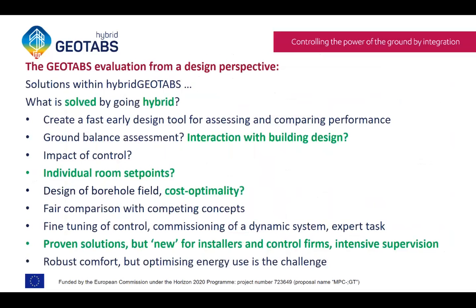So if we go hybrid, if we add that second system, what have we solved? We've solved the issue of interaction with the building design — the building doesn't have to be perfectly balanced regarding heating and cooling demands. We can put the balanced part on the ground, and the leftover on the secondary emission system. Individual room set points, by adding the secondary system, are also solved. If the director of the company wants a slightly hotter temperature in his room, he can just activate the thermostat and the secondary emission system will react, while the TABS still provide the largest share of heat to the building.